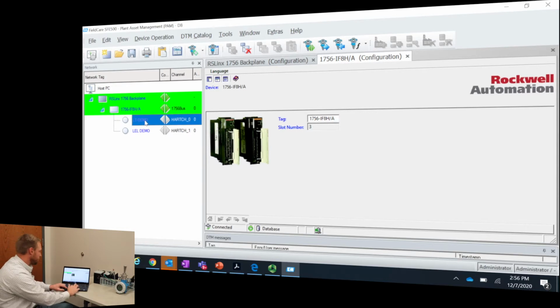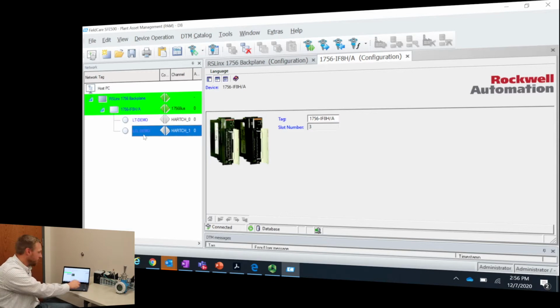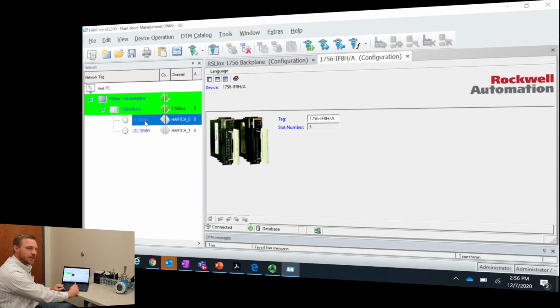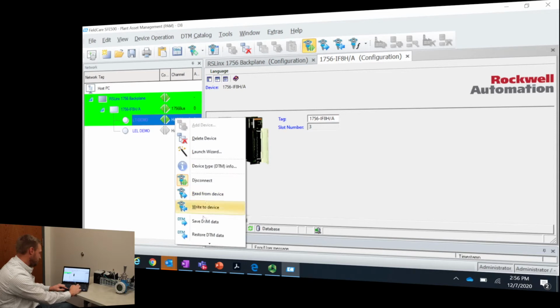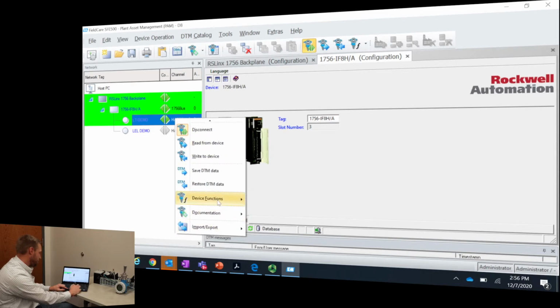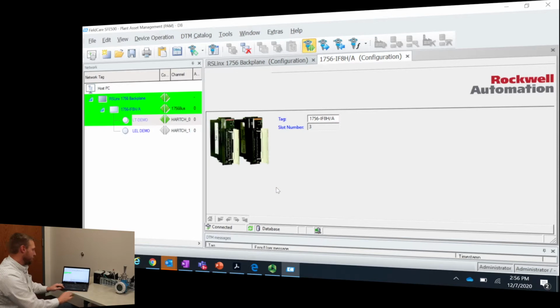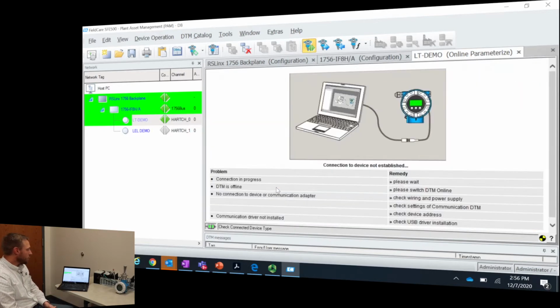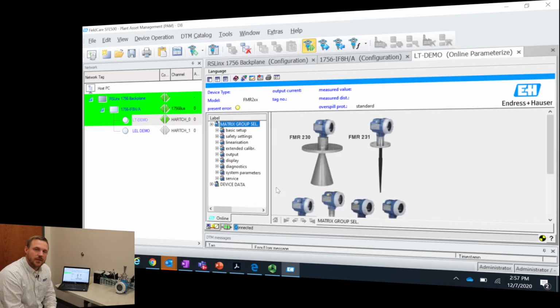You'll see we have 2 devices here, LT demo and LEL demo. LT, level transmitter demo, and LEL, lower explosive limit demo. We'll first connect to the LT demo. Okay, we're connected. Now we'll go online. Online parameterized. Again, this will take a little bit of time for this information to load since it's all getting done over HART communication. But as you see, it's slowly pulling in.